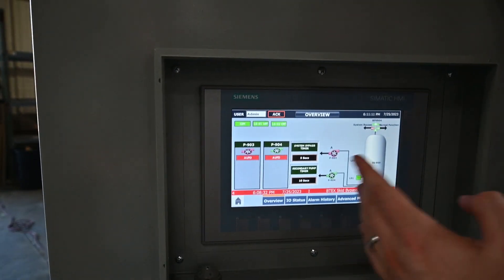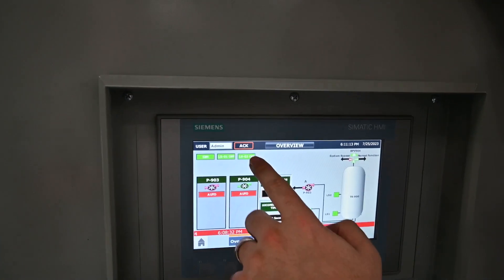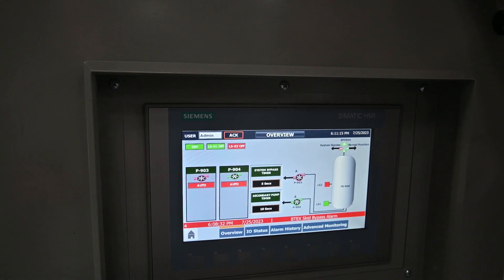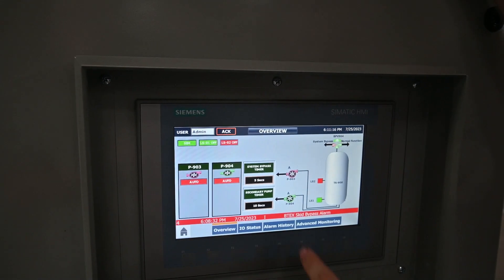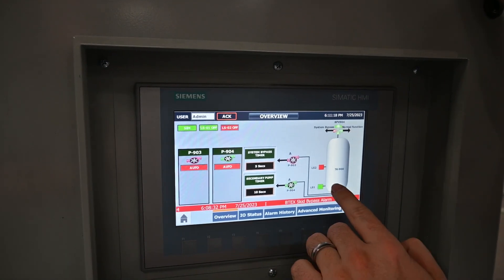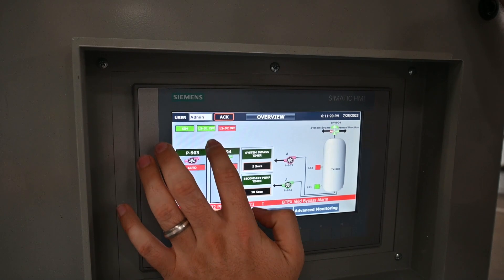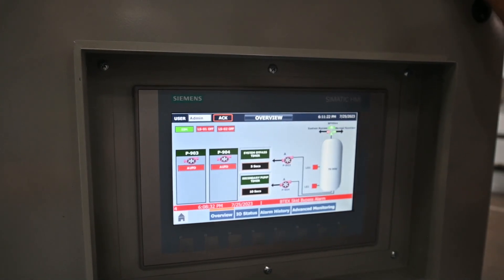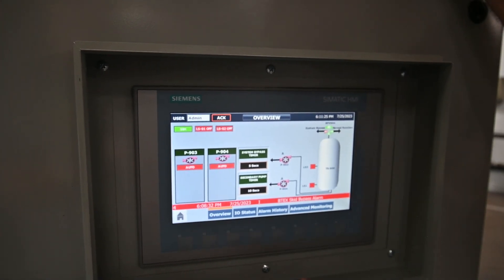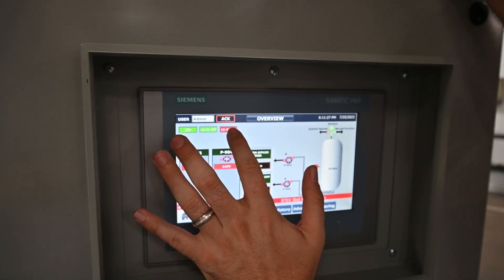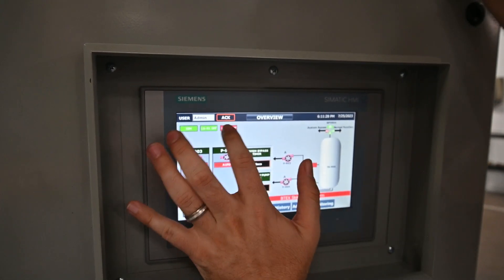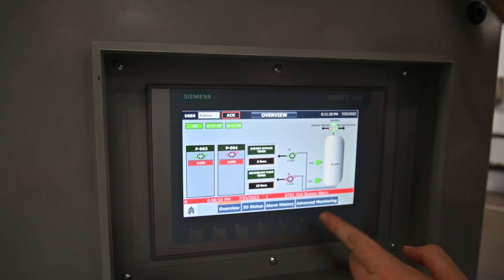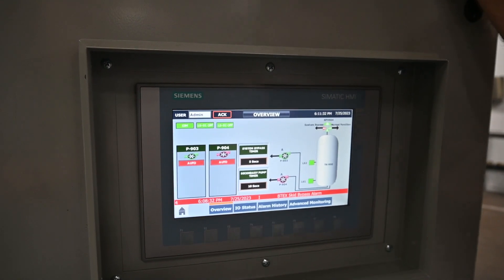Under normal conditions, it will immediately go back below level switch two, and your pump will stay running until it reaches LS1 again. It goes back up, condensate begins to increase again. It'll go to LS1, it'll hit the LS2 mark, and it now alternates your pumps.